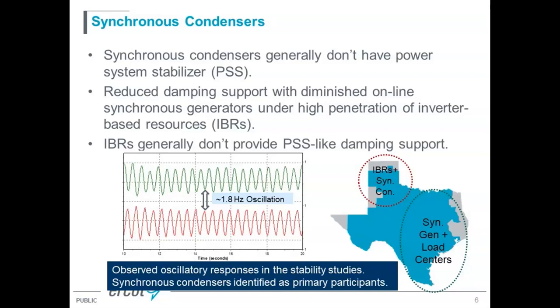inverter-based resources also do not provide a PSS-like function, for example power oscillation damping. Along with the high penetration of inverters, the diminished online synchronous machines also leave the system with less and less damping support. The simulation result on the slides is just one example we observed in the stability analysis. Look at the map on the bottom: we have a high penetration of inverter output focused in West Texas. In that whole region, we only have inverters and synchronous condensers in the panhandle.